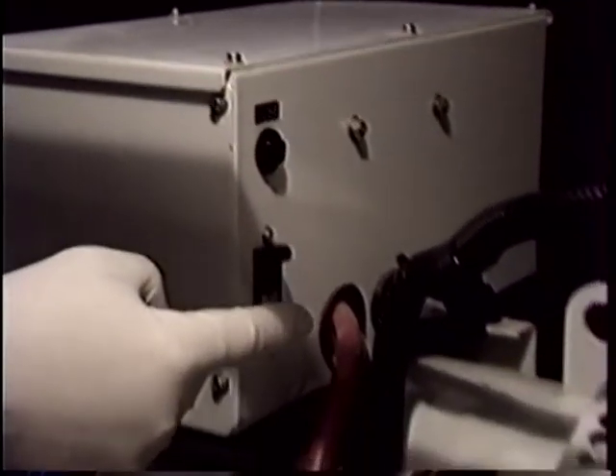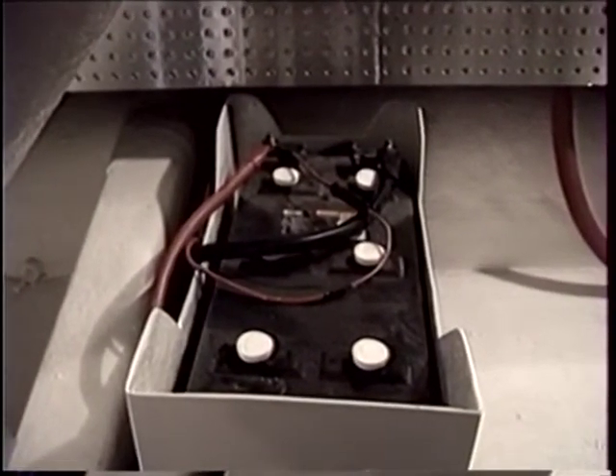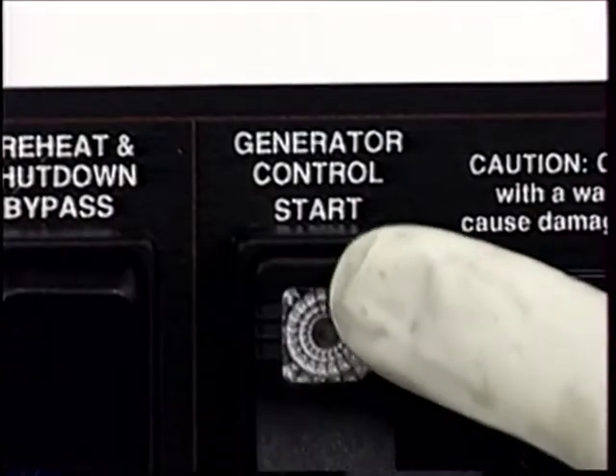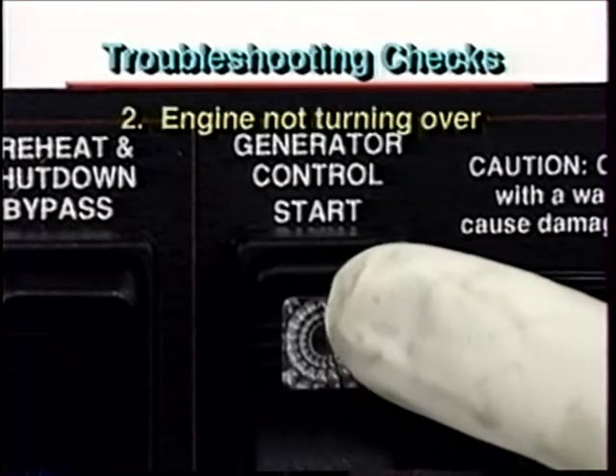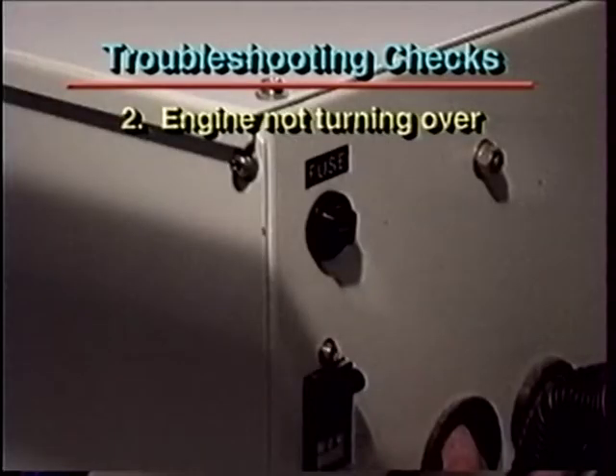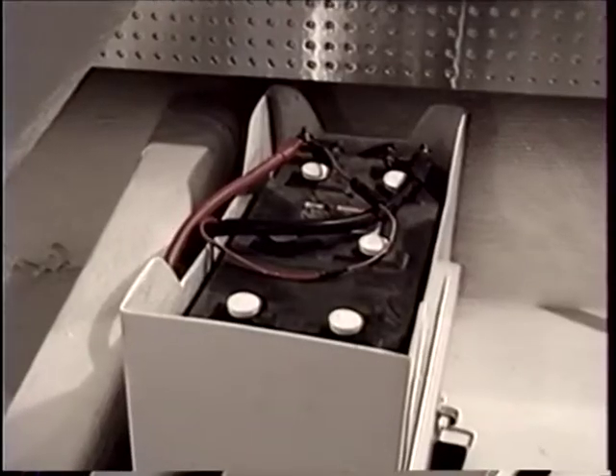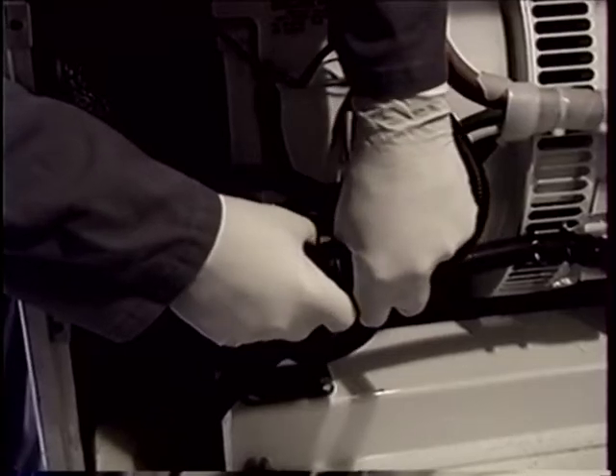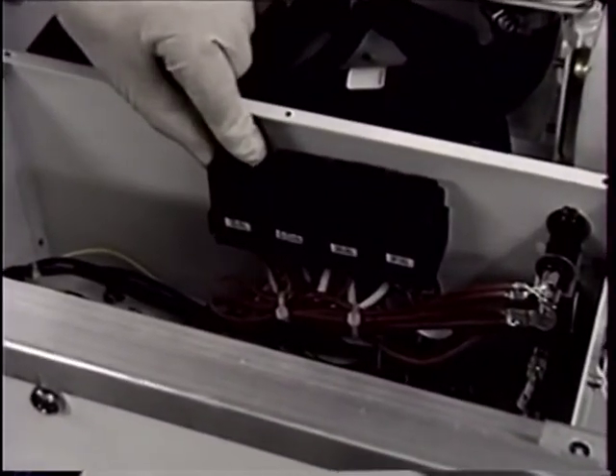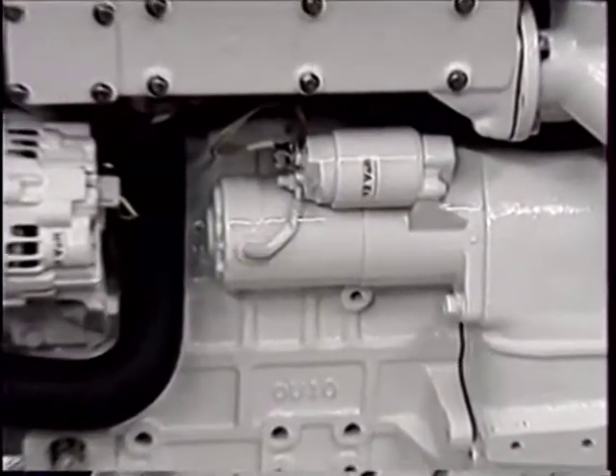Note that the Northern Lights generator sets require 12 or 24 volts DC to run, so if you should lose battery voltage from a tripped DC circuit breaker, broken wires, relays, or a dead battery, the generator set will stop. Common reasons for the engine not starting because it won't crank over are a tripped DC circuit breaker located on the generator junction box, a discharged battery, a bad connection of the wire harness to the control panel, a problem with the control relay, or a problem with the starter itself.